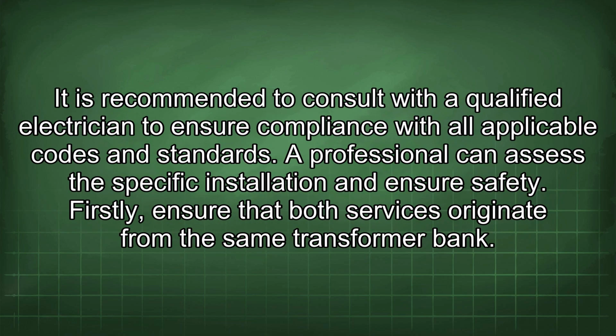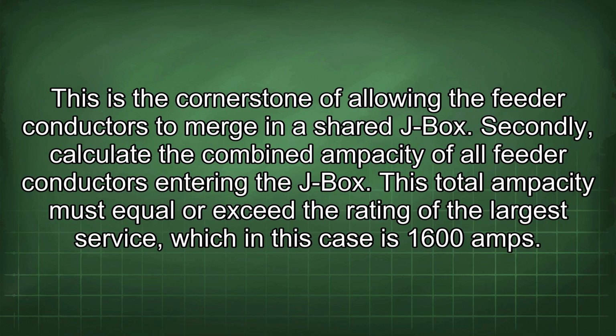It is recommended to consult with a qualified electrician to ensure compliance with all applicable codes and standards. A professional can assess the specific installation and ensure safety. Firstly, ensure that both services originate from the same transformer bank. This is the cornerstone of allowing the feeder conductors to merge in a shared J-box. Secondly, calculate the combined ampacity of all feeder conductors entering the J-box. This total ampacity must equal or exceed the rating of the largest service, which in this case is 1600 amps.